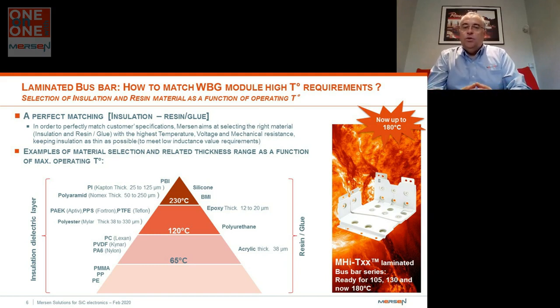So to address this, it's better to use laminated busbar technology. However, using laminated busbar in such a high temperature environment required us to develop new technology to withstand that temperature range. So far, we have put on the market three ranges of laminated busbar: one dealing up to 105 degrees C, another up to 130 degrees C, and the very latest one, able to achieve up to 180 degrees Celsius.